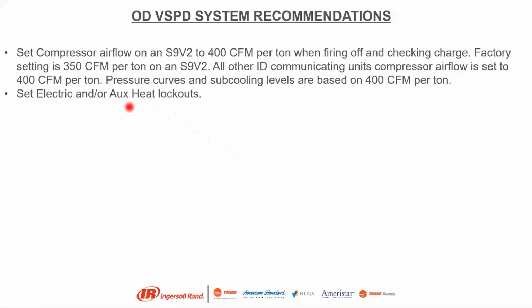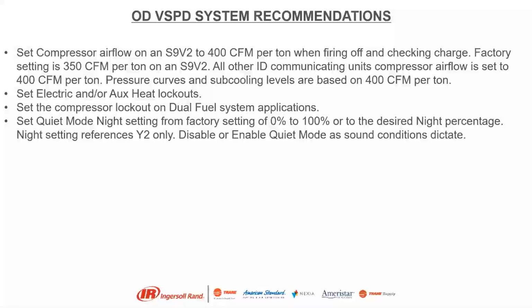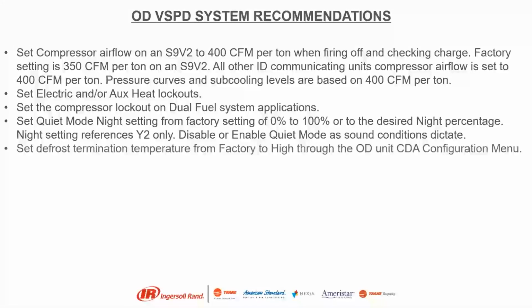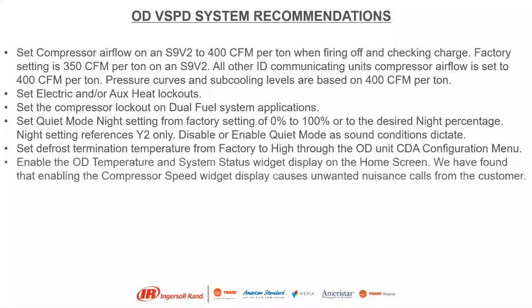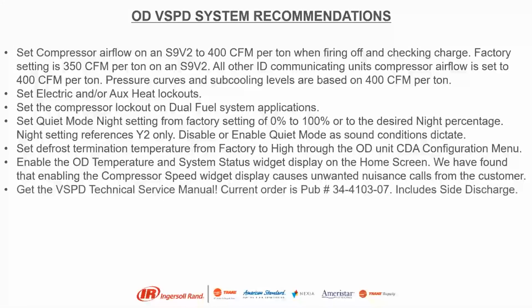Set your electric heat, auxiliary heat lockouts. Again, this is just recommendations. Set the compressor lockout, set quiet mode, set defrost termination factory. Again, I have a printout, so if you'd like this emailed to you too, it's just a checklist that you can give out to any new installers, any seasoned installers, just to go through and confirm that they are completing everything.